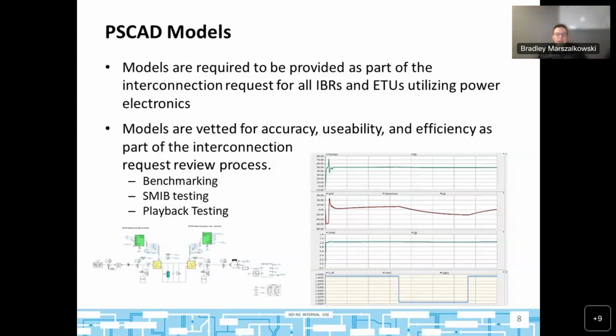Internet problems. So we require all new interconnection requests to include an EMT model usable in PSCAD. The models are vetted for accuracy, usability, and efficiency before the system impact study starts. These are things we can check ourselves by putting the model into PSCAD and running it in a SMIB type system—checking that the droop is set to what they say it is, or that voltage control is enabled using whatever scheme they reported.